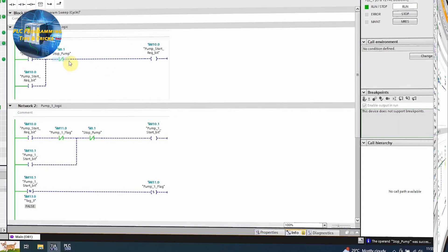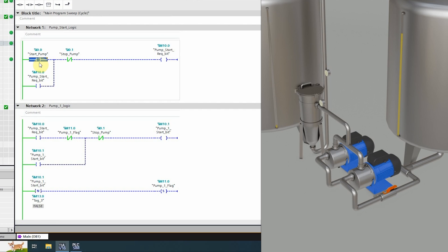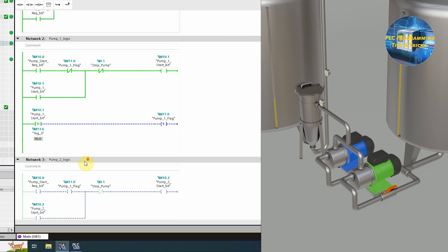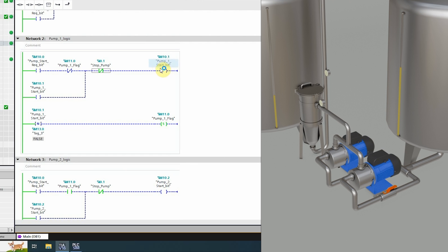As you can see, as soon as we press the start pump button I0.0, it will latch on the pump start request bit M10.0. In network 2, you can see that the pump start request bit is closed and this pump 1 flag bit is already closed. This will latch on the pump 1 start bit M10.1. Now if we press the stop pump button I0.1, it will turn off pump 1 start bit M10.1, and on its negative edge it will set on the pump 1 flag M11.0. This pump 1 flag bit M11.0 is now opened up and will prevent pump 1 from starting on the next pump start request.